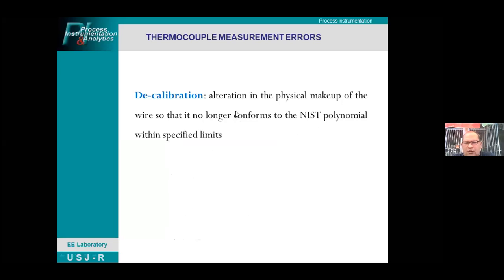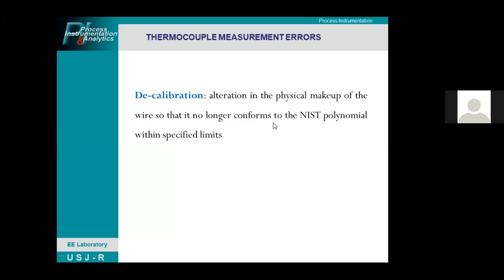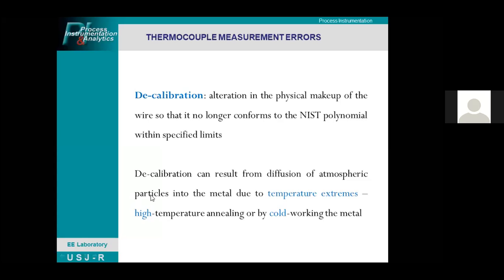Then for the decalibration, it is the alteration in the physical makeup of the wire so that it no longer conforms to the NIST polynomial within specified limits. So during the decalibration of the unit, there are changes where the wires will be replaced, changed into other types of wire. So the result could be non-conformance to the specified limits. So that will be possible during the decalibration, the alteration of the physical makeup of the wire. The decalibration can result from diffusion of atmospheric particles into the metal due to temperature extremes, high temperature annealing, or by cold working the metal. So that will be possible as a source of error in thermocouple measurements.